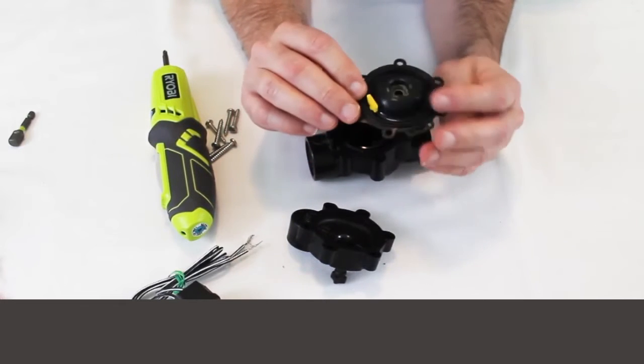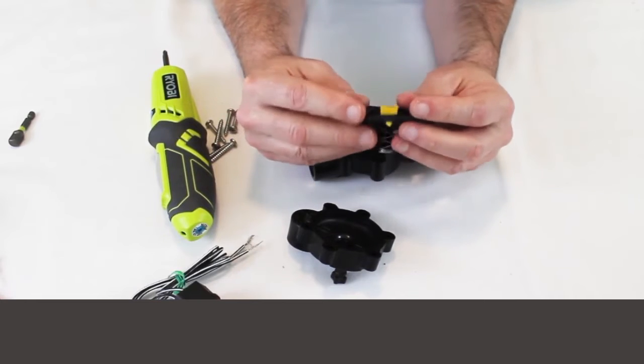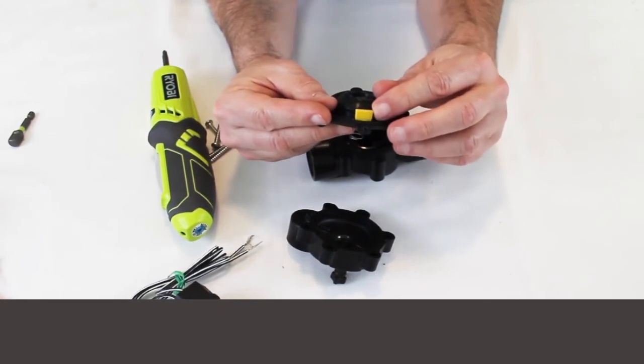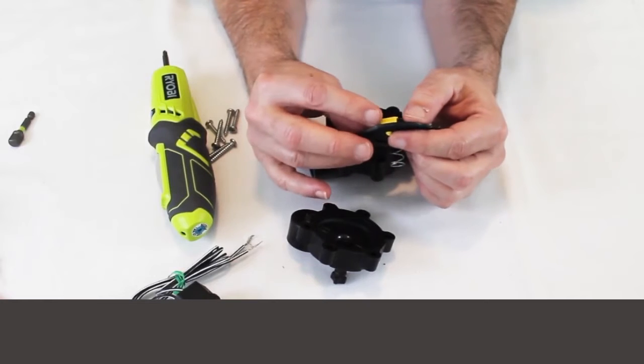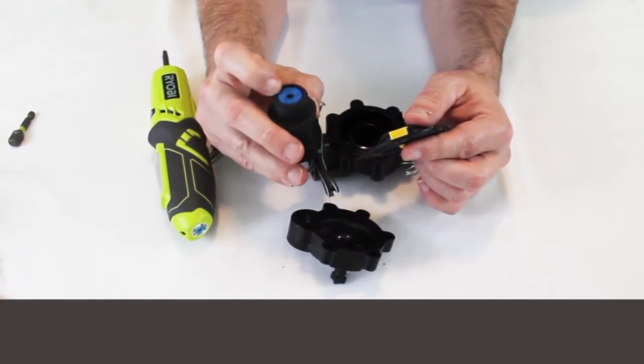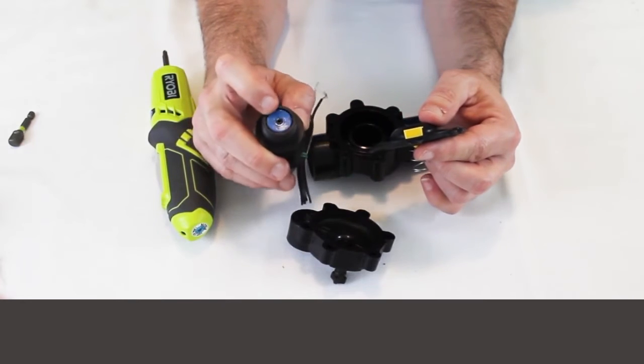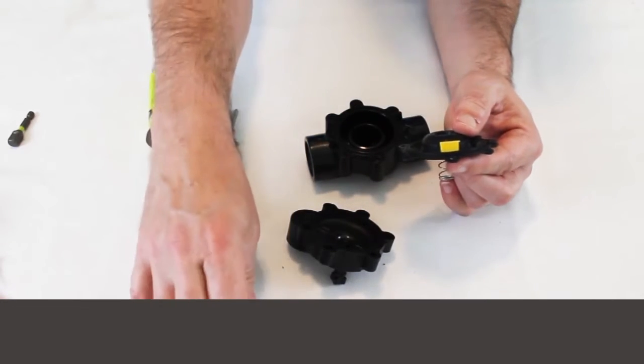Take a look here on the bottom. If you're putting the original parts back in, if you're just cleaning it out, this is a little tiny filter on here. That helps. There's actually two filters in the DV, one here, and then the piece here that's the encapsulator for the solenoid plunger is actually a little bit of a filter itself.